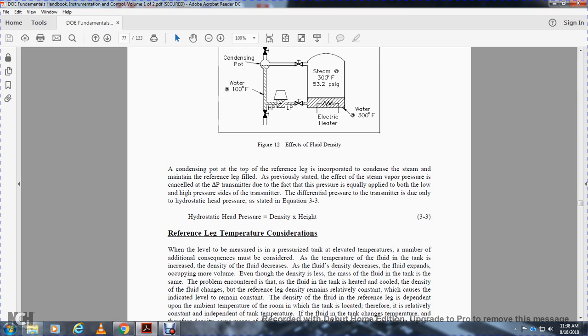The temperature is maintained with condensate from the steam, keeping the reference leg as previously stated. The effect of the steam vapor pressure cancels in the differential pressure of the transmitter, because the pressure is equally applied to both the low and high pressure sides of the transmitter. The differential pressure for the transmitter is due only to the hydrostatic head pressure, as shown in Equation 3-3. Hydrostatic head pressure is equal to the density times the height.